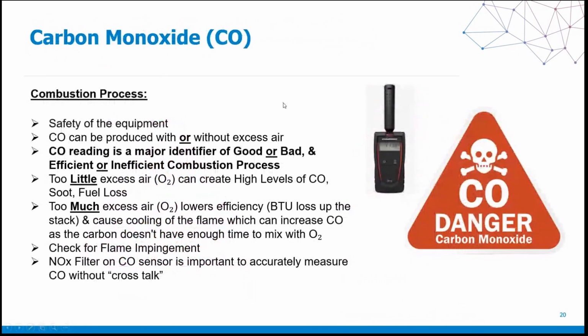And when we talk about CO, it comes down to a few different things. First of all, obviously it's occupant safety, but we also have to look at the safety of the equipment. It's a major identifier of how our combustion process is proceeding. Obviously, with very high levels of CO, you're going to have very low levels of oxygen, and those levels are going to be unstable. And when you have high levels of CO, you're creating a potentially hazardous condition.